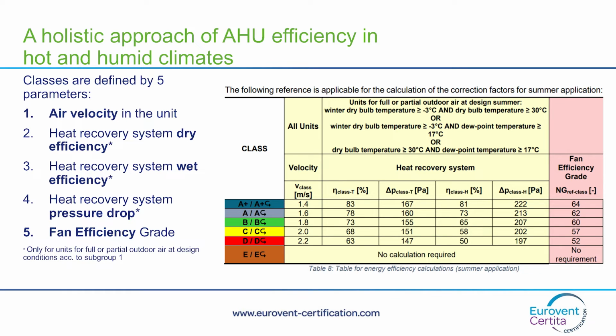This new energy label covers what we could call summer applications, including heat recovery efficiency for both dry and wet efficiency, so covering both dry and humid energy recovery. We take into account the heat recovery pressure drops, the fan efficiency grade, and the air velocity in the unit. So it's a quite holistic approach which takes into account all aspects of an air unit in order to provide, with a single letter, the efficiency of the unit.